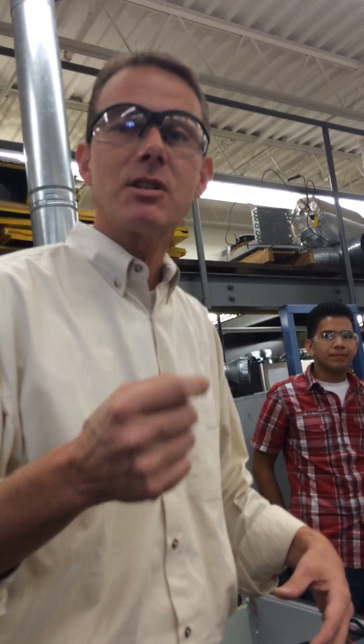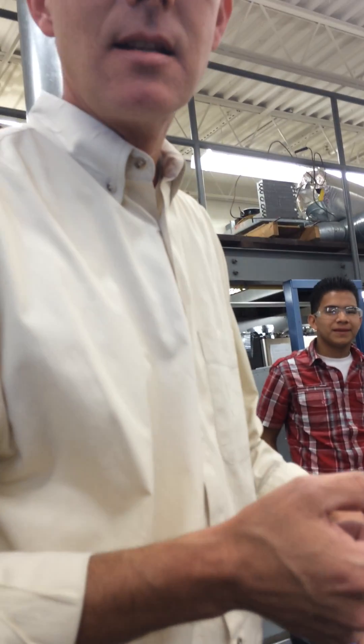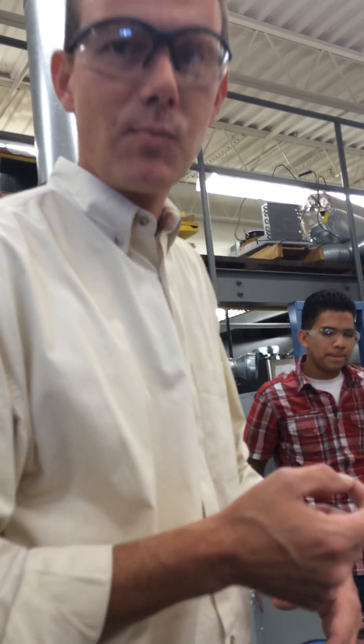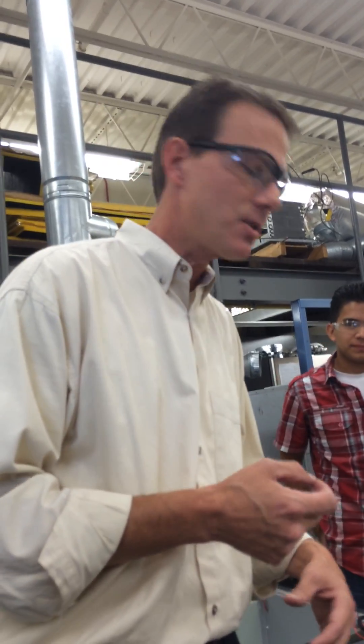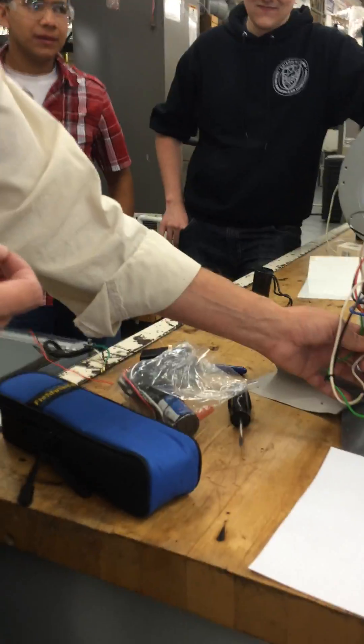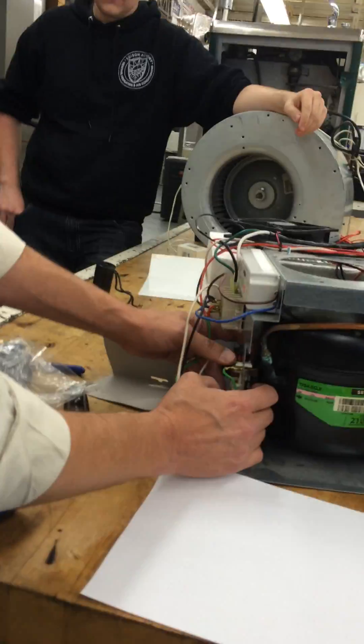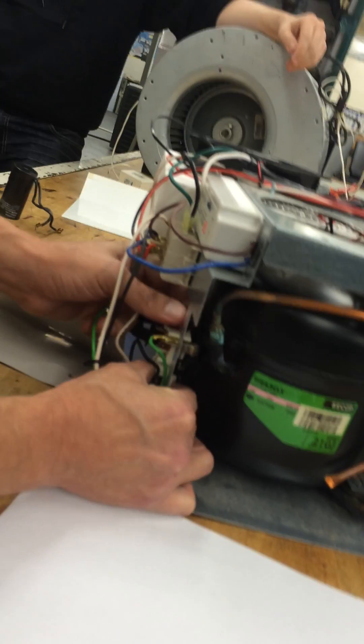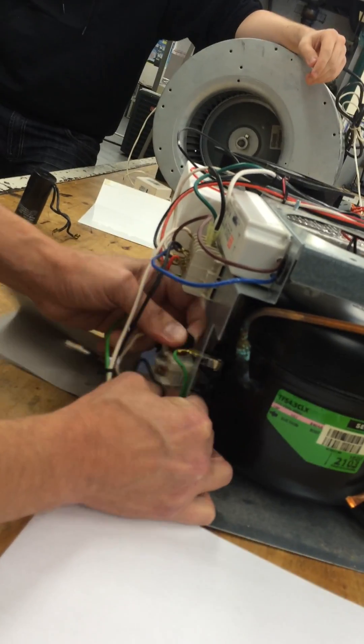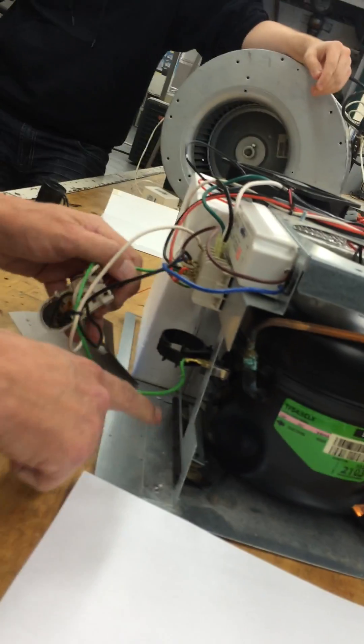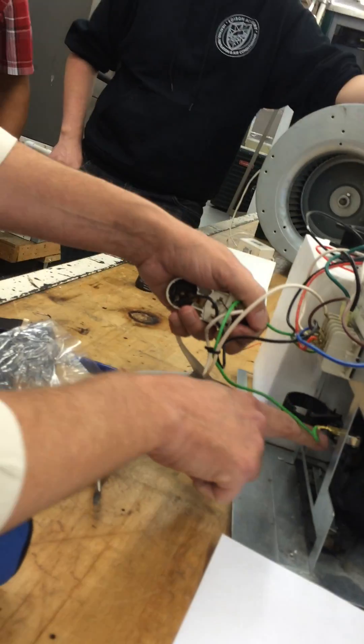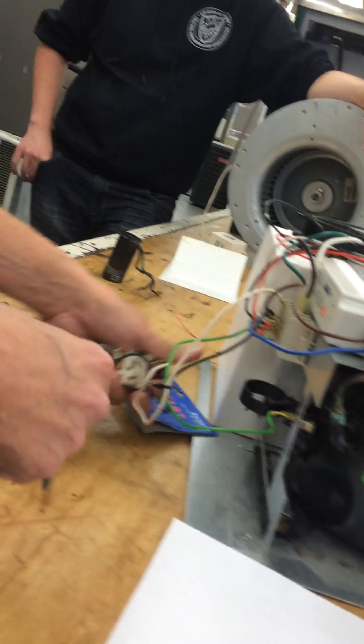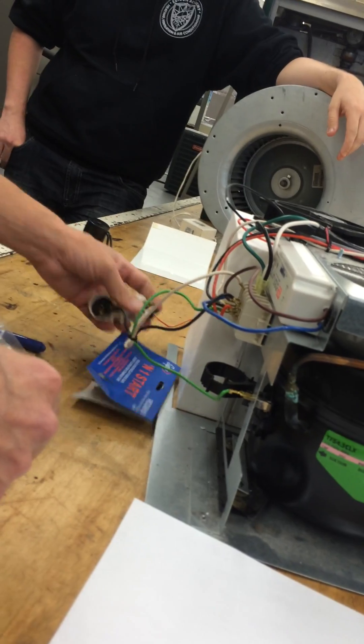All right, this is how to find common start run on a single phase compressor. So what we got here is we have a start kit, and we're going to replace our start relay with the start kit. But when we pull it off, we don't have anything identified common start run.